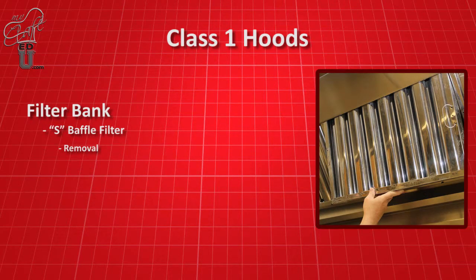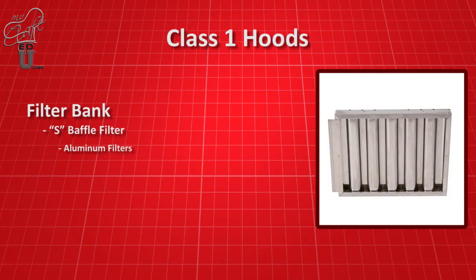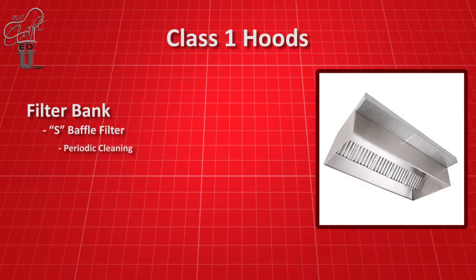S-filters are easily removed for cleaning by raising the filter slightly and sliding the bottom out. S-filters are available from manufacturers in aluminum or stainless steel. Now, even the best filter systems do not remove all of the grease from the airstream. Periodic cleaning of the ductwork will need to be performed by a licensed professional.